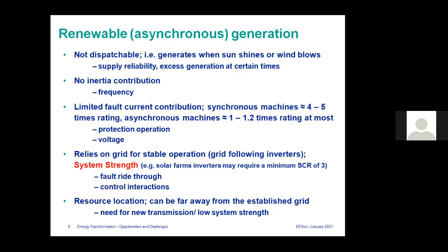One other issue is the inertia contribution, because synchronous generators, we all know, contribute inertia to the system. And inertia helps with frequency control. The higher the inertia in the system, when there is a change or disturbance, the frequency change takes time. But with residential solar or even other utility solar and wind, normally there is no major inertia contribution. But things are changing. Now those technologies are picking up. I am talking more about the traditional inverter-based generation, which is more grid following. But now people are talking about grid forming inverters, machine modes and like that. They are working on running the asynchronous generation like synchronous machines. So it's happening, but right now the inertia loss is a major issue when you reduce synchronous machines in the system.